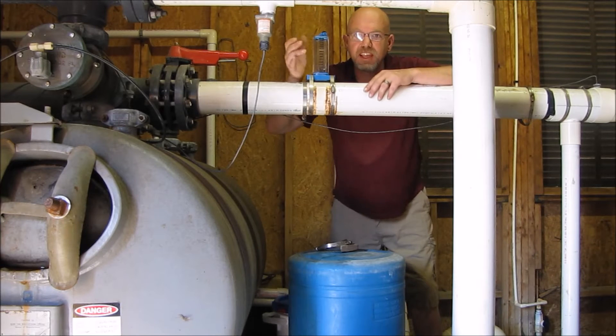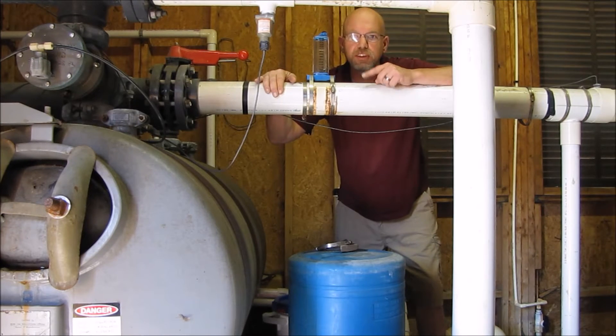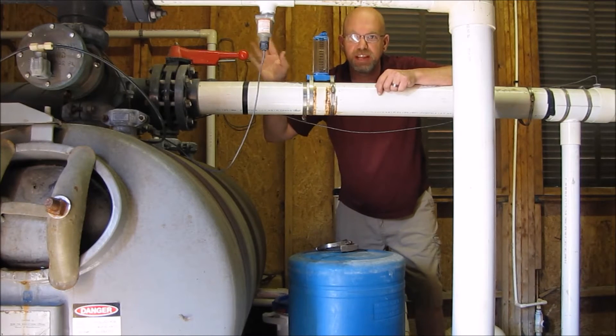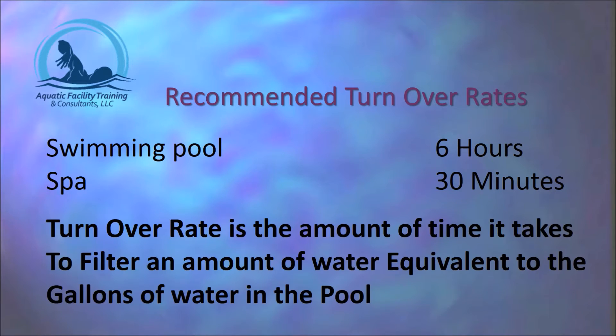This is your flow meter. It tells you how much water is actually moving through the system at any time. We use this to determine whether or not we're meeting the correct turnover rates for the pool. The recommended turnover rate for a swimming pool is once every six hours. For a spa, the recommended turnover rate is once every 30 minutes. Turnover rate is the amount of time it takes to filter an amount of water equivalent to the gallons of water in the pool.